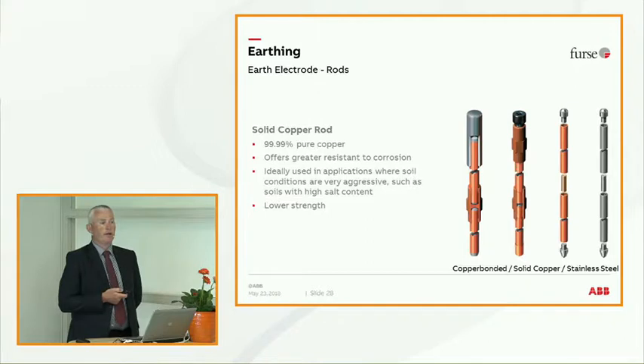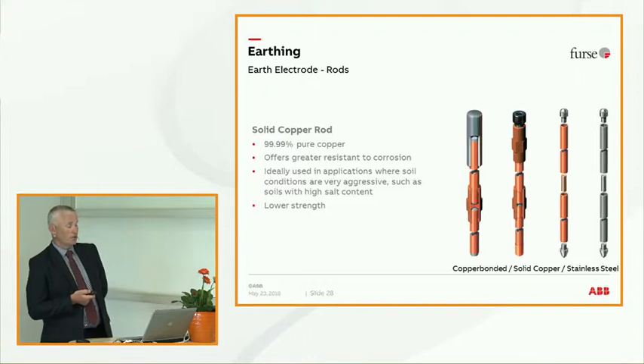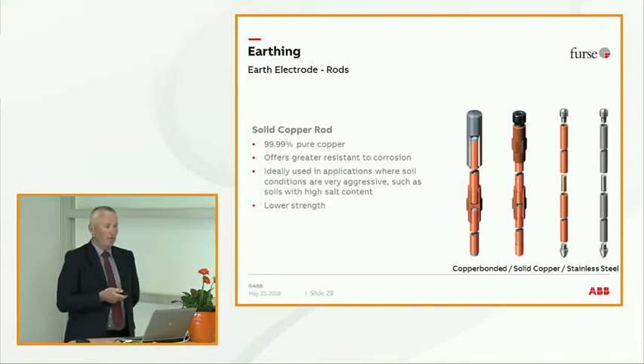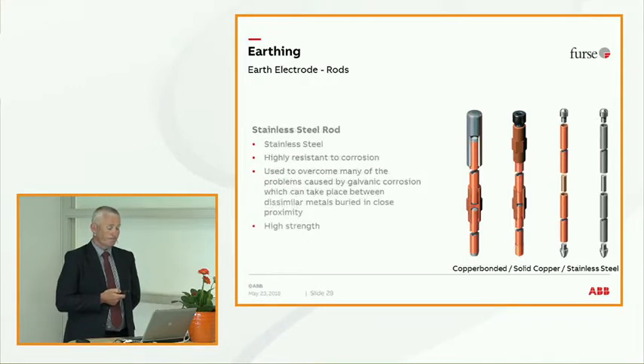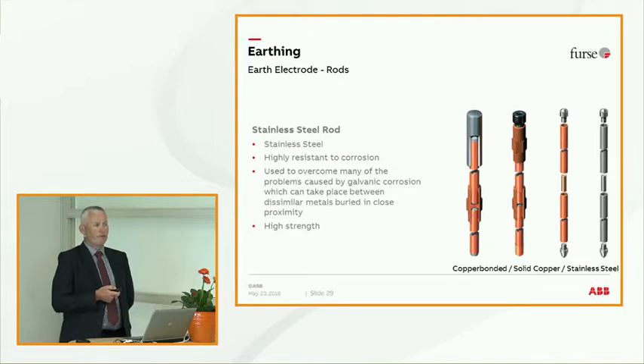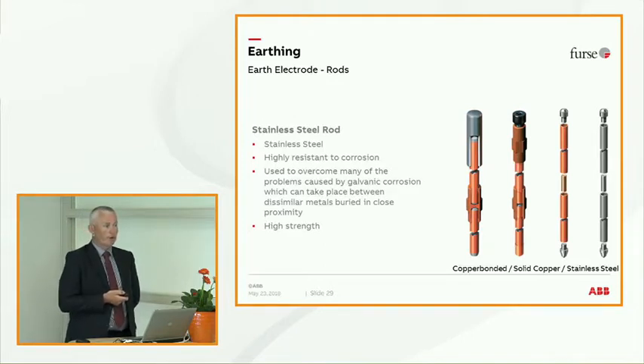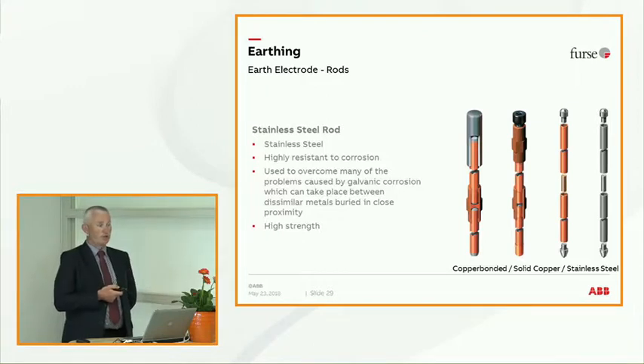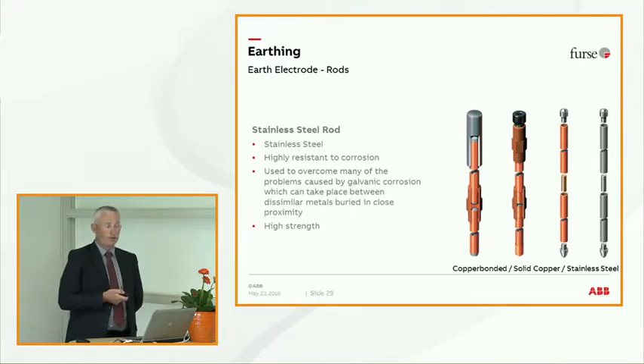If you've got instances where you could have a corrosive soil, you may require better earth readings. Certain regions, particularly the Middle East, often opt for solid copper rods. The problem being they're then very expensive, but they are very good and they'll last a long time. So they're used in applications where you will get a better reading, but then the commercial aspect will come into play. We also do a stainless steel rod. If you've got high pH systems and even copper can be corroded, then they might opt for a stainless steel rod. Again, certain regions and certain applications will ask for these stainless rods. So we as a company and organisation recommend copper bond, solid copper or stainless.